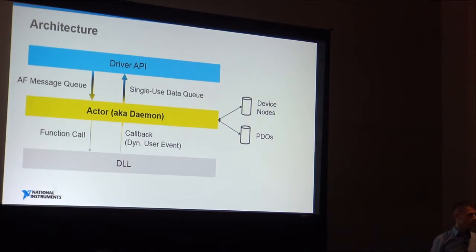Remind us what the PDO is. It's a process data object, sorry. Basically, that's a collection of 8 data bytes that are assignable, so that you can configure the node, for example, to send medium temperature, supply voltage, and stuff like that. Just do that continuously without having to call. Calling, exactly. That was a good transition.